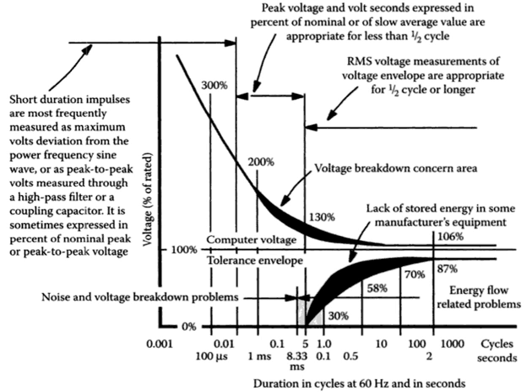Topic: frequency. Variations in the frequency. Non-zero low frequency impedance. When a load draws more power, the voltage drops. Non-zero high frequency impedance. When a load demands a large amount of current, then stops demanding it suddenly, there will be a dip or spike in the voltage due to the inductances in the power supply line. Variations in the wave shape, usually described as harmonics at lower frequencies, usually less than 3 kHz, and described as common mode distortion or interharmonics at higher frequencies.